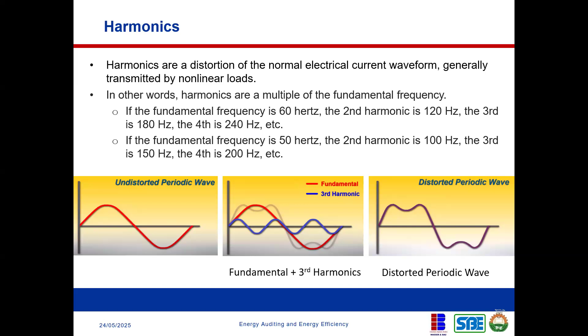So what are the causes of harmonics? Harmonics are generated by solid state-based equipment, just like I explained. They are generated by solid state-based equipment, such as the switching power supplies in your PCs and other electronic systems, your DC drives, your variable frequency drives, your electronic ballasts, your arc welders. If you look through this list, you will realize that all of these items are things that convert your alternating current to a DC current. And the same thing goes for your LED bulbs.